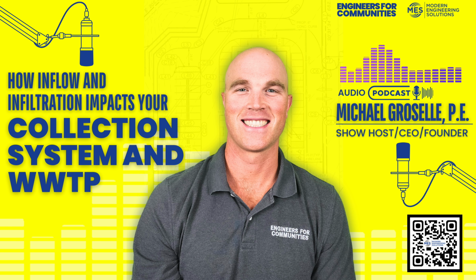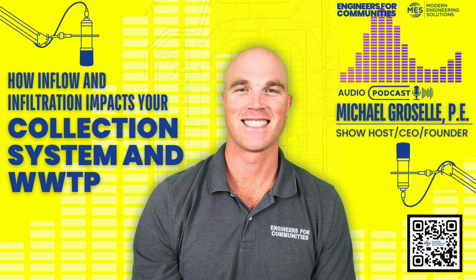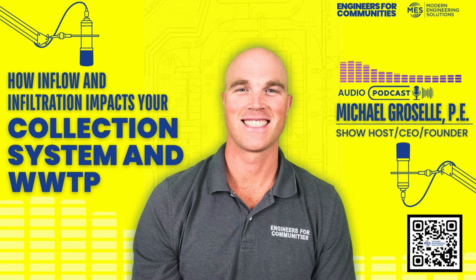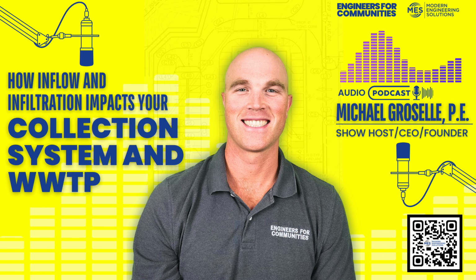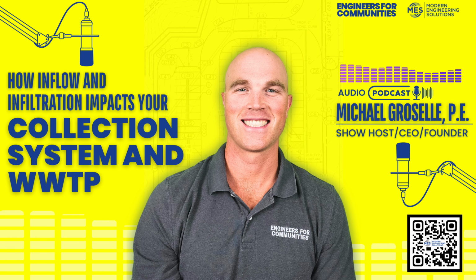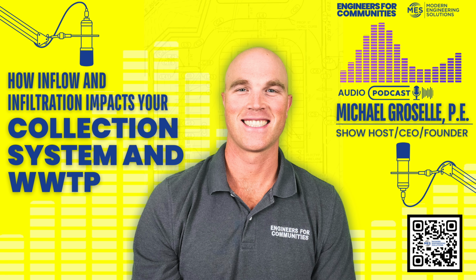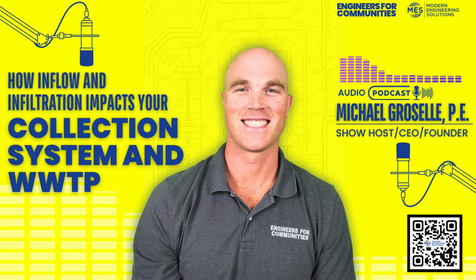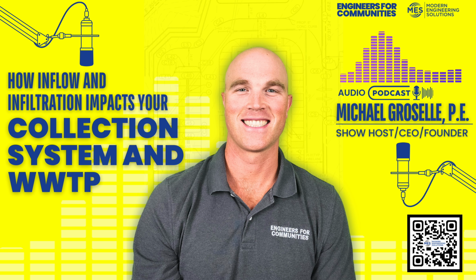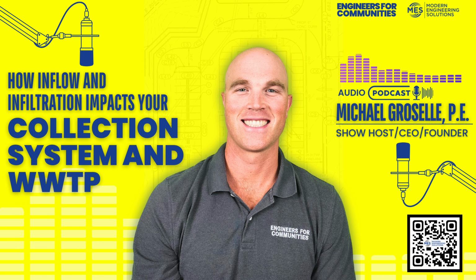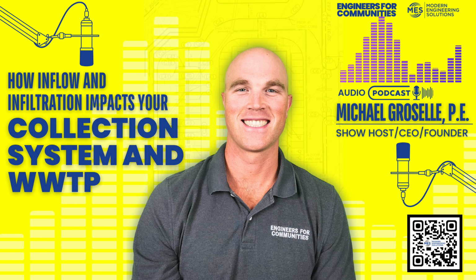Okay, so dye testing. You see this green gooey stuff from that slime show on Nickelodeon when we were all kids. What you can do is put this non-toxic dye into a groundwater system or stormwater. And if it appears in your sewer, let's just say I go over to this inlet in the road and I dump some of this dye into it, and it ends up a couple manholes down the street in a sanitary manhole, well, this would show that there's a cross connection, and we'd want to go fix that and figure out where it's connecting in that specific section of pipe.